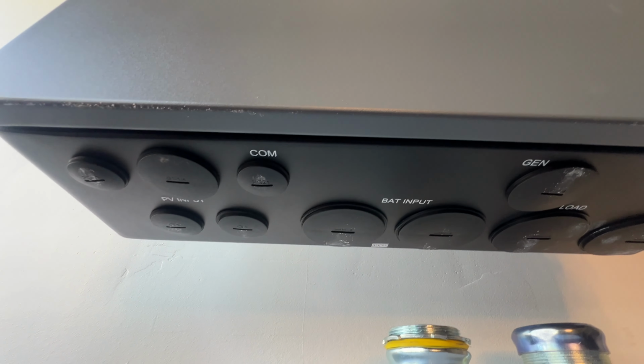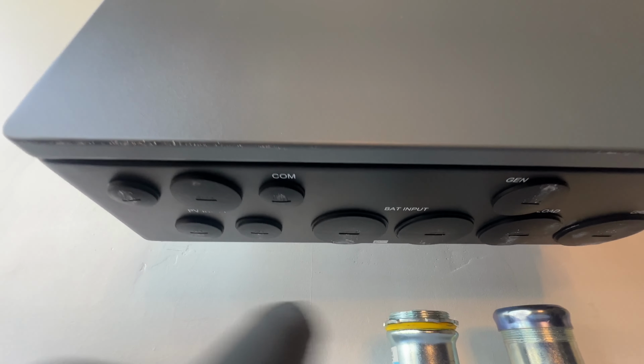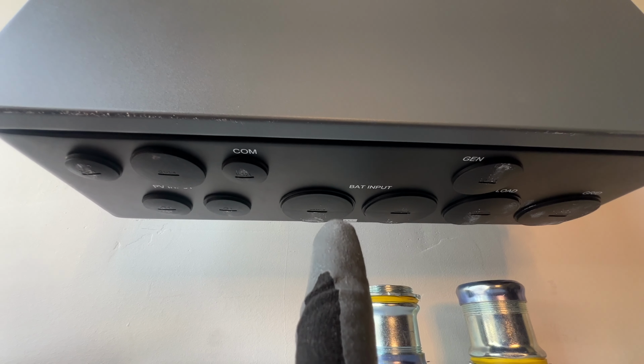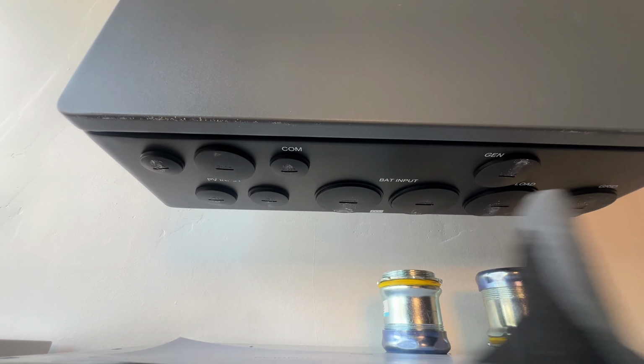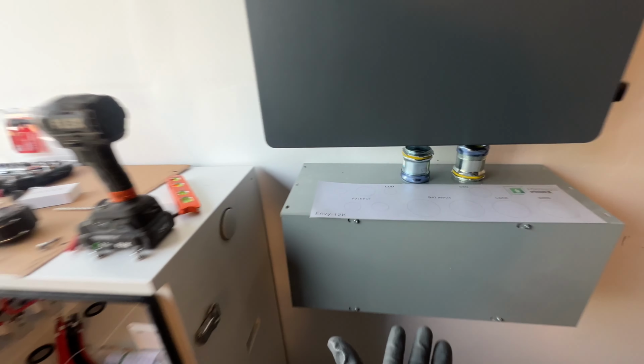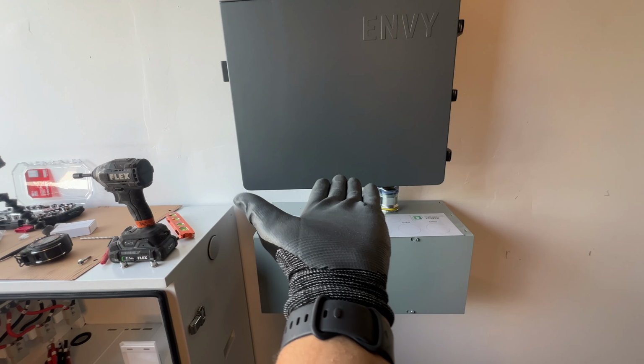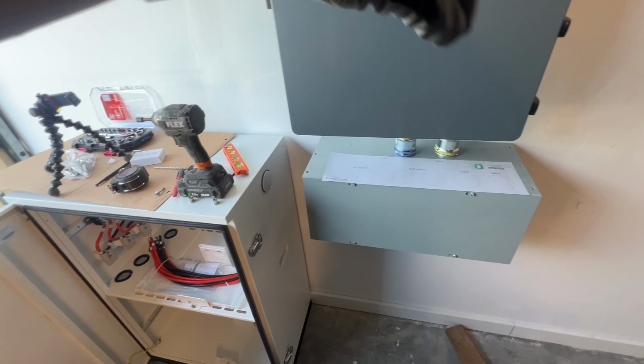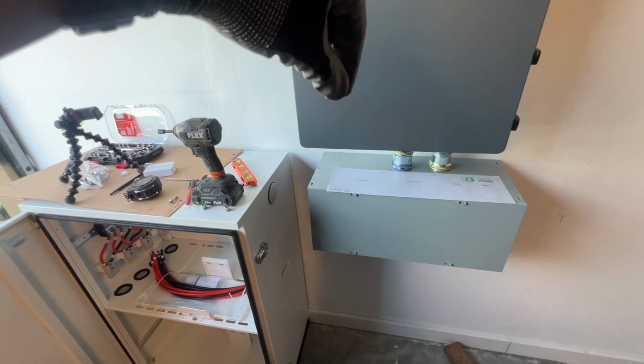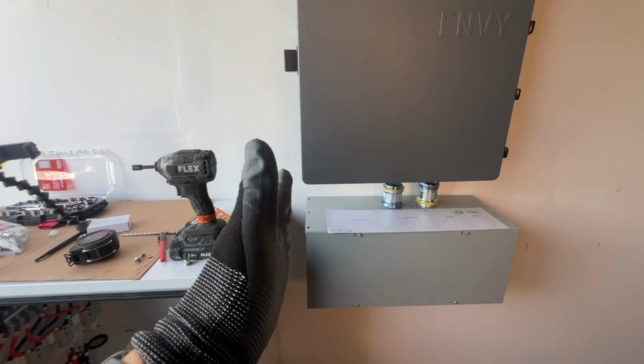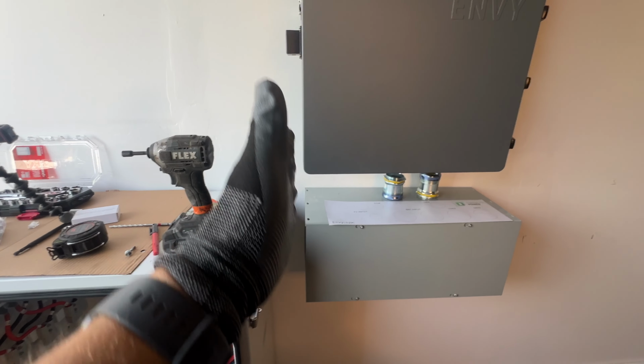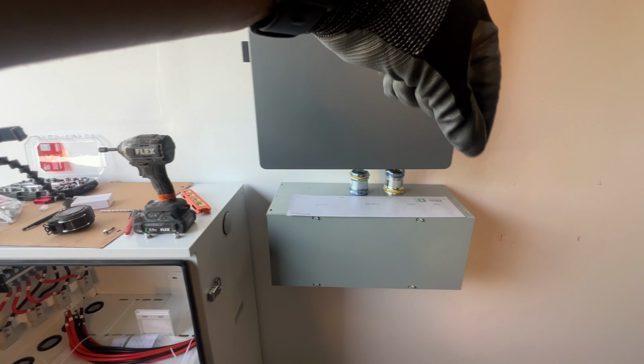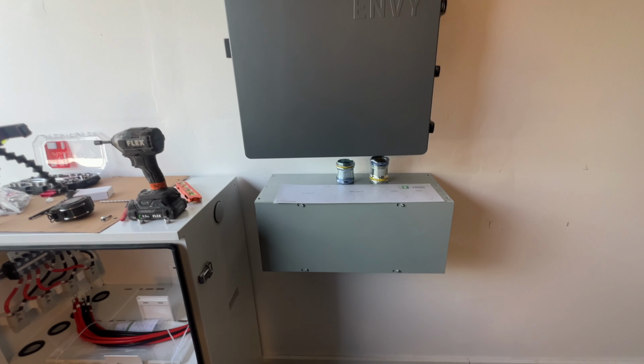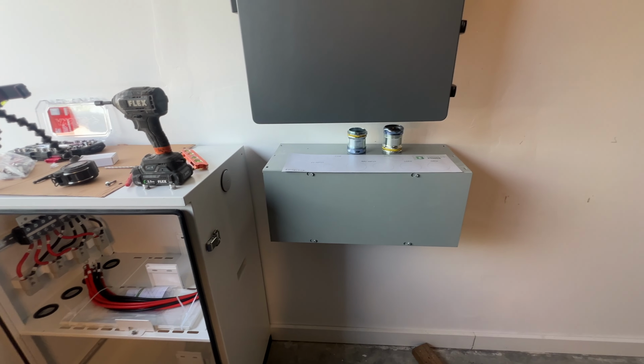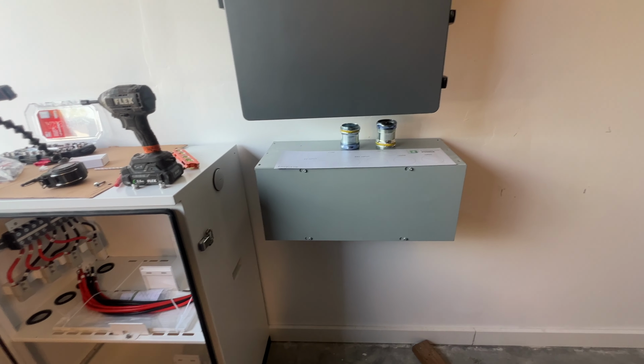I think the best way to do this, honestly, is to just select what runs you're going to do and then take all those conduits up. I'm going to lift the gutter up to the bottom, and then from the inside, trace those holes so I have an idea of where everything's going. Since I have this lined up flush, I can keep that side flush with the inverter and trace out my holes so I know my conduit is running straight down for the position of the inverter. So I'll make those marks and start cutting them.